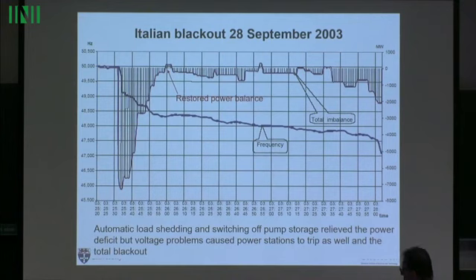But the problem was there were huge swings of frequency and the voltage dropped. So you started to lose power stations, because power stations are quite complicated equipment with a lot of pumps pumping water and everything. If there's a problem with frequency and especially voltage, those pumps stop working, and then the power station disconnects.